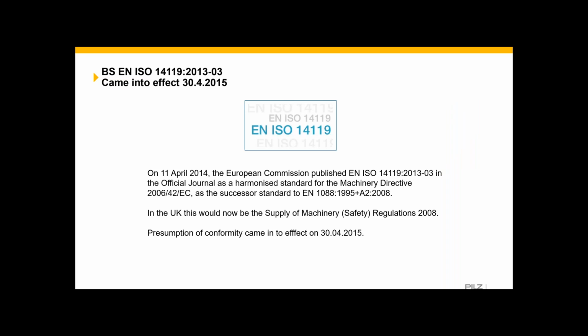So 14119. Presumption of conformity to the machinery directive came into effect in 2015, and in the UK this would now be the Supply of Machinery (Safety) Regulations 2008. This standard is relevant to anyone that manufactures interlocking devices or uses interlocking devices. So that covers OEMs such as PILZ, OEMs of machines, and end users alike.